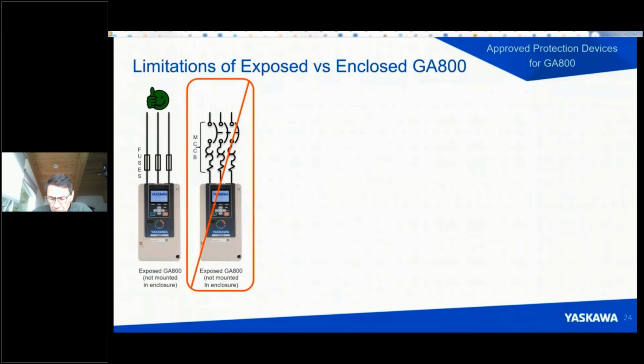We were allowed to use that to protect a number of drives in the past, such as A1000. Now, is the fundamental design of the A1000 much different than the GA800? It is not any different. It's just that the rules for releasing a product are different now than what they were when we released the A1000 10 years ago, even though both of these products are listed and released under UL 508C.